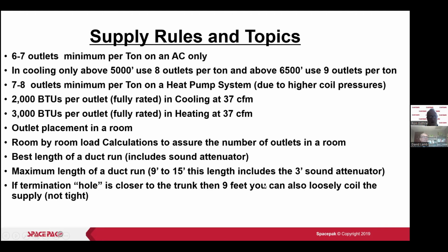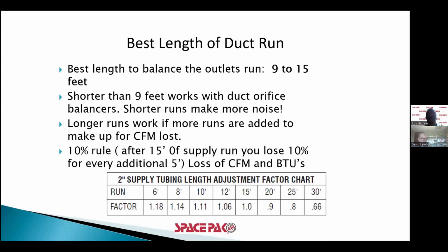6 to 7 outlets minimum per ton on AC. If you're above 5,000 feet, 6,500 feet, you need more outlets to compensate for that. 7 to 8 outlets minimum per ton on a heat pump due to higher coil pressures. 2,000 BTUs cooling, 3,000 BTUs heating. And I think we have actually done that slide.